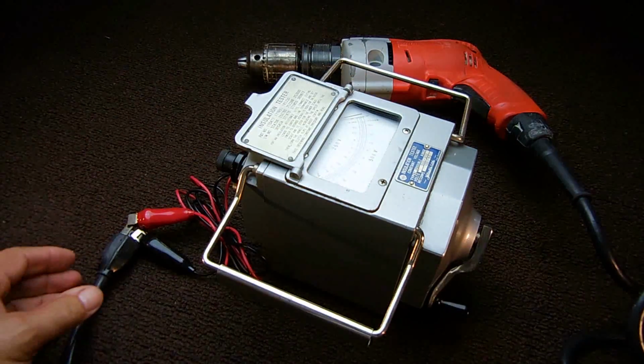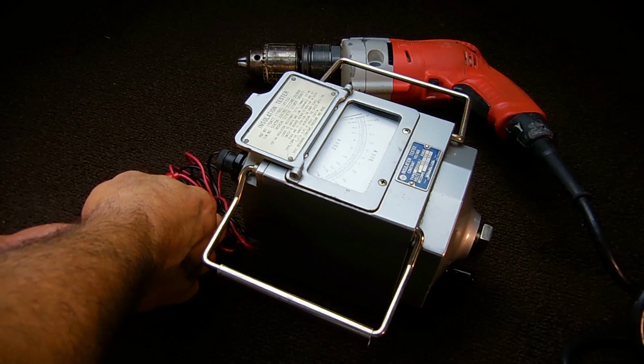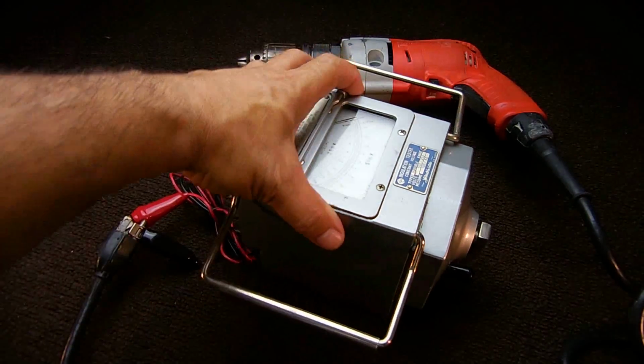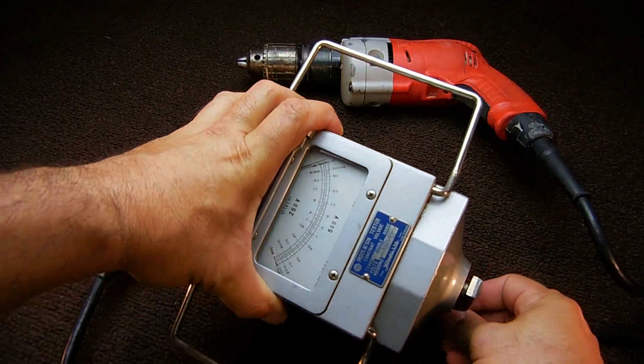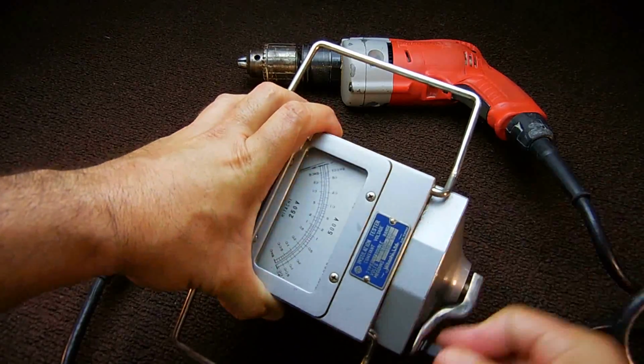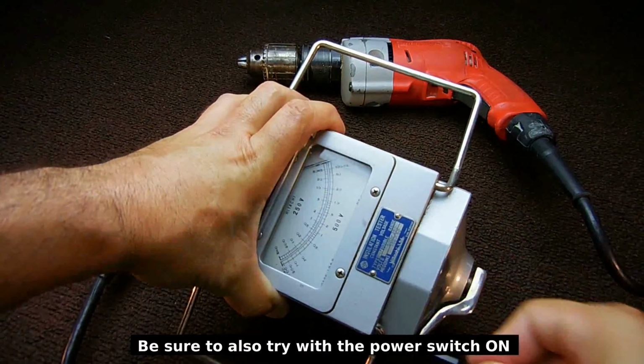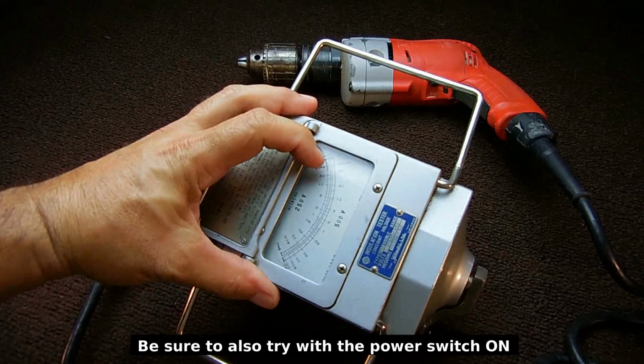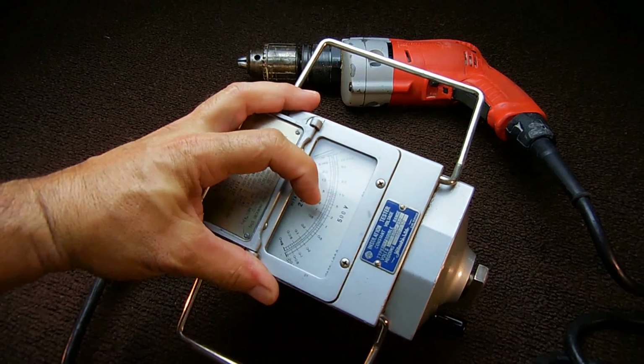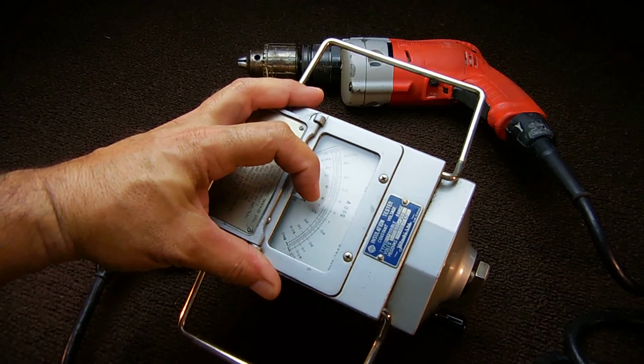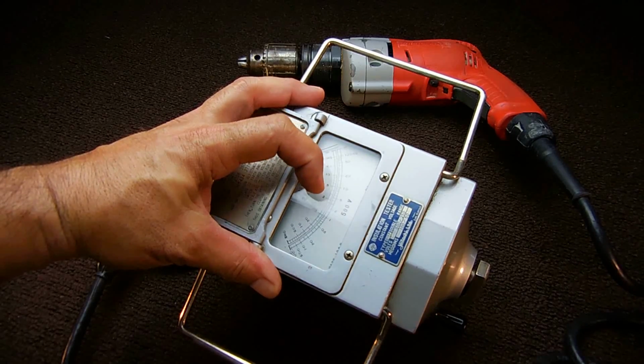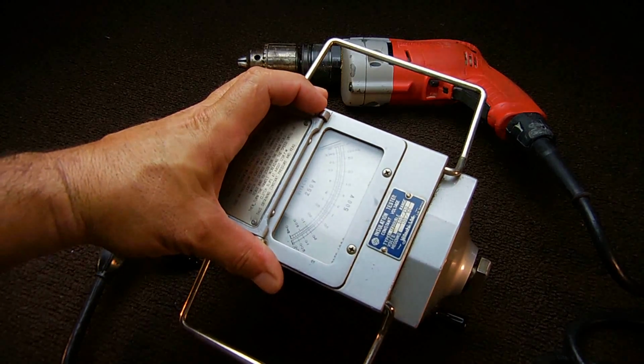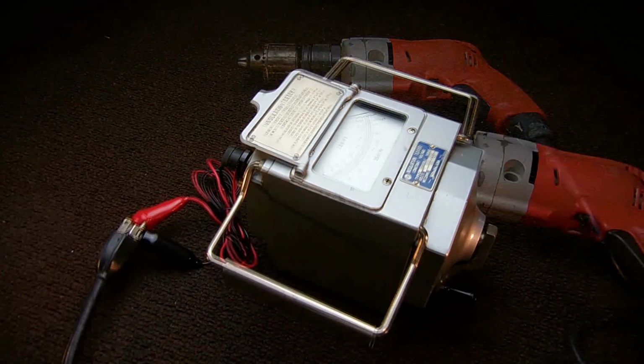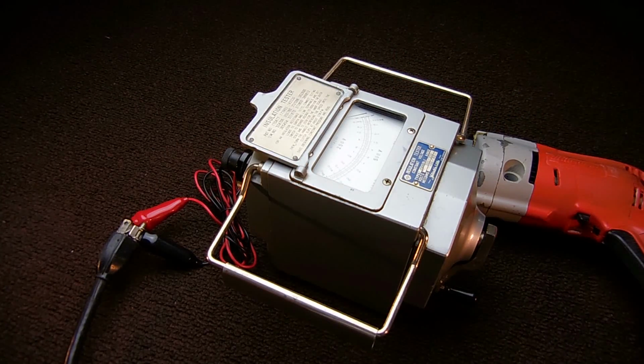Alright. Now I'm going to go over to the other pin. If you saw the needle swing all the way down and it went towards the 2 area or lower, you're going to know you got a problem there, and that motor is going to be prone to failure in the very near future. Remember, you don't want to test between the neutral and the hot. You want to check between the neutral and the ground and the hot and the ground.